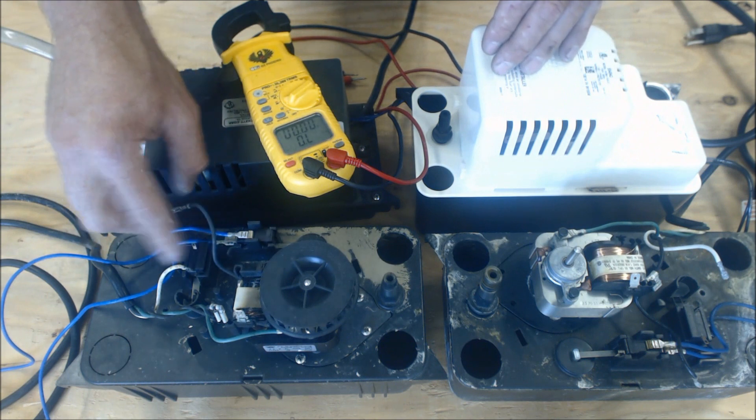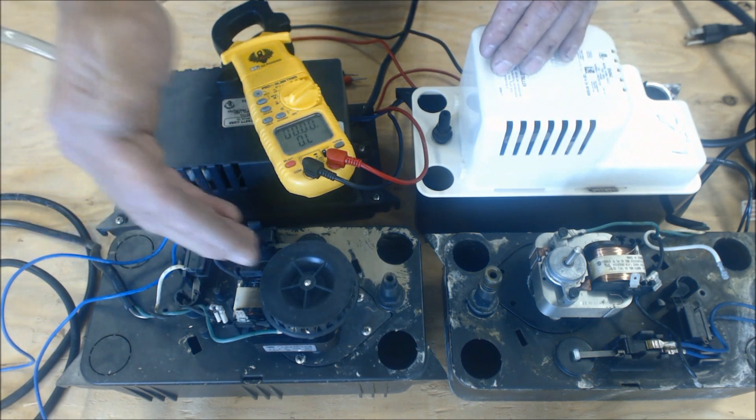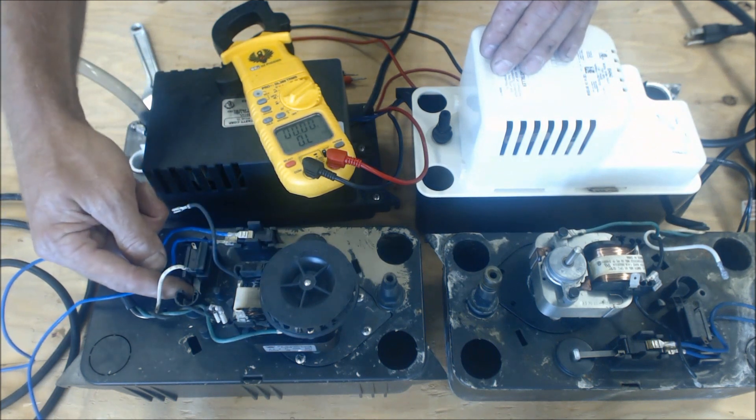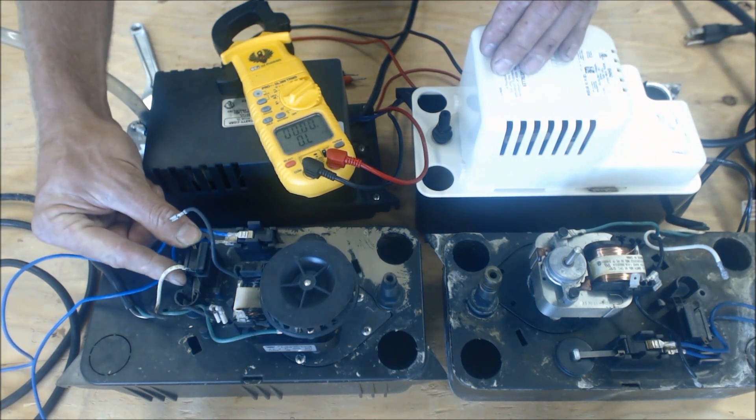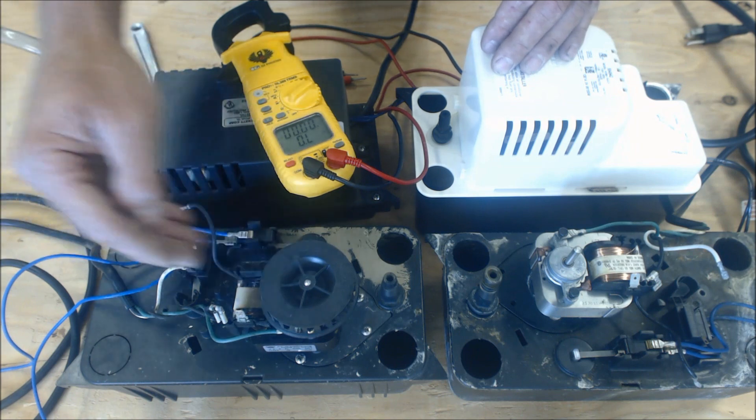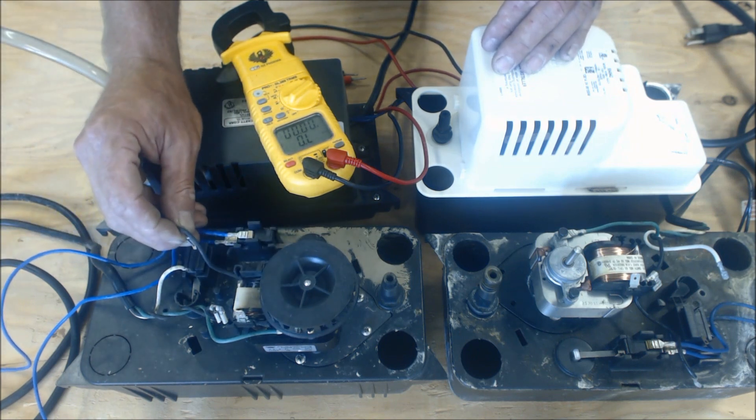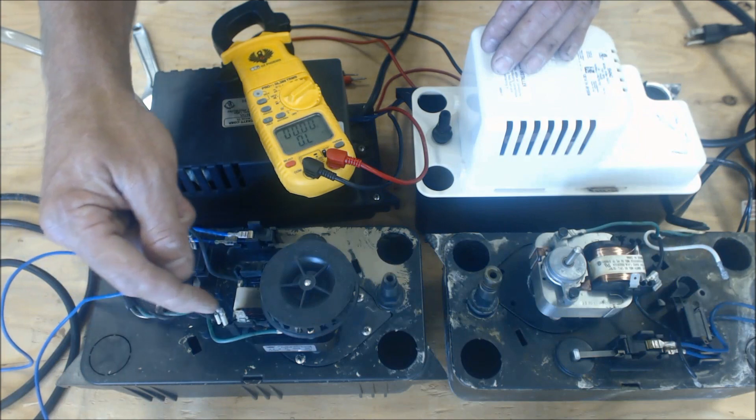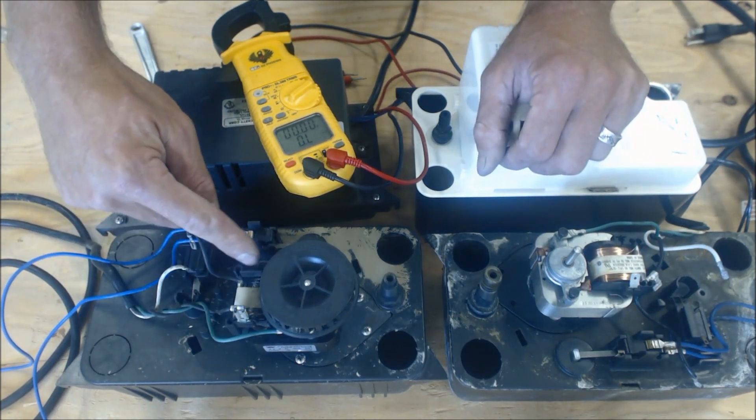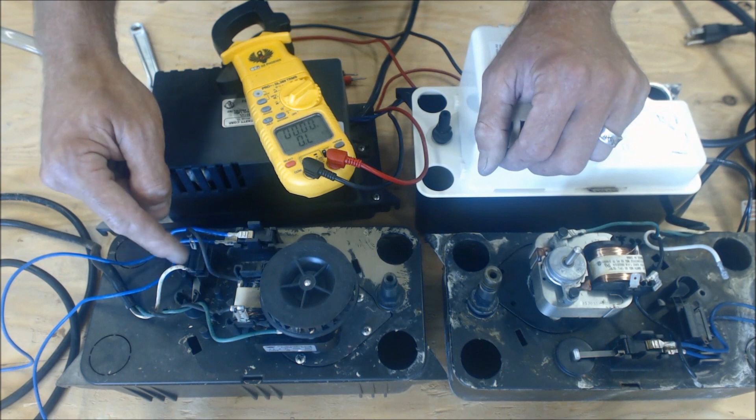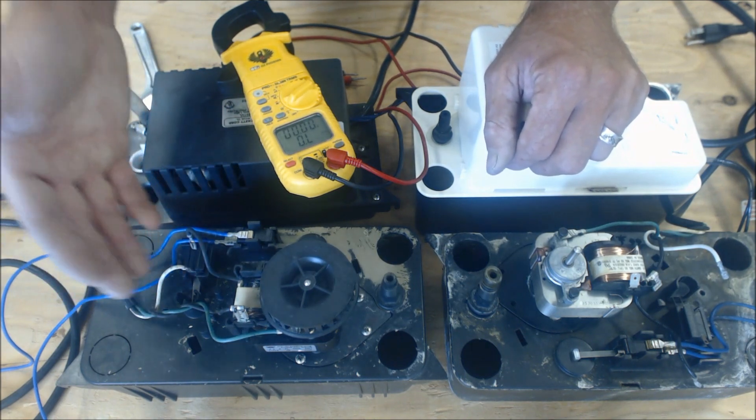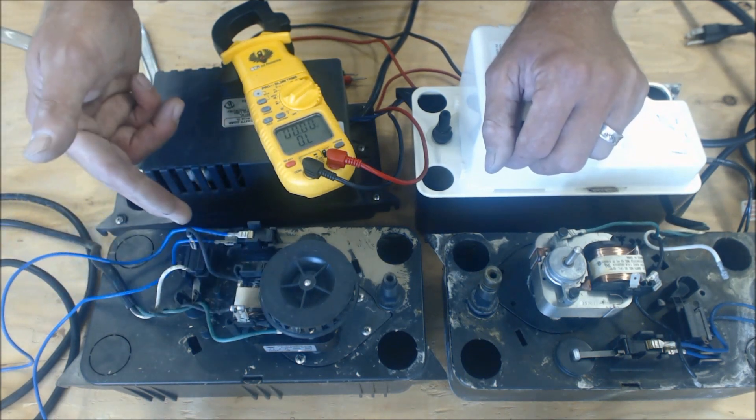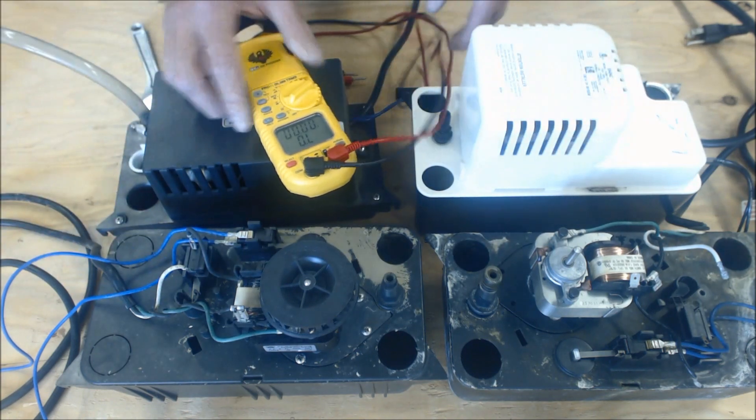These switches right here, this micro switch actually turns the pump on and turns it off. So when this is up all the way, it's going to close this switch and it's directly in line with the motor wiring. So what you have is you have the hot wire going straight to the pump, and then it comes out, and it's actually breaking your common. Most motors you're usually breaking your hot, these ones happen to break the common coming back.